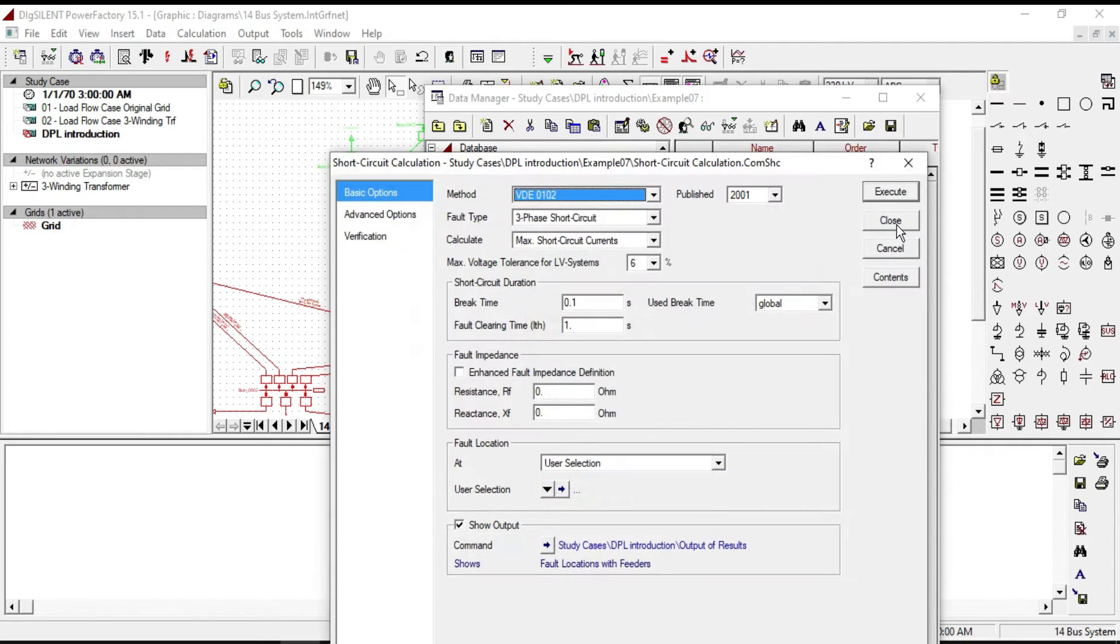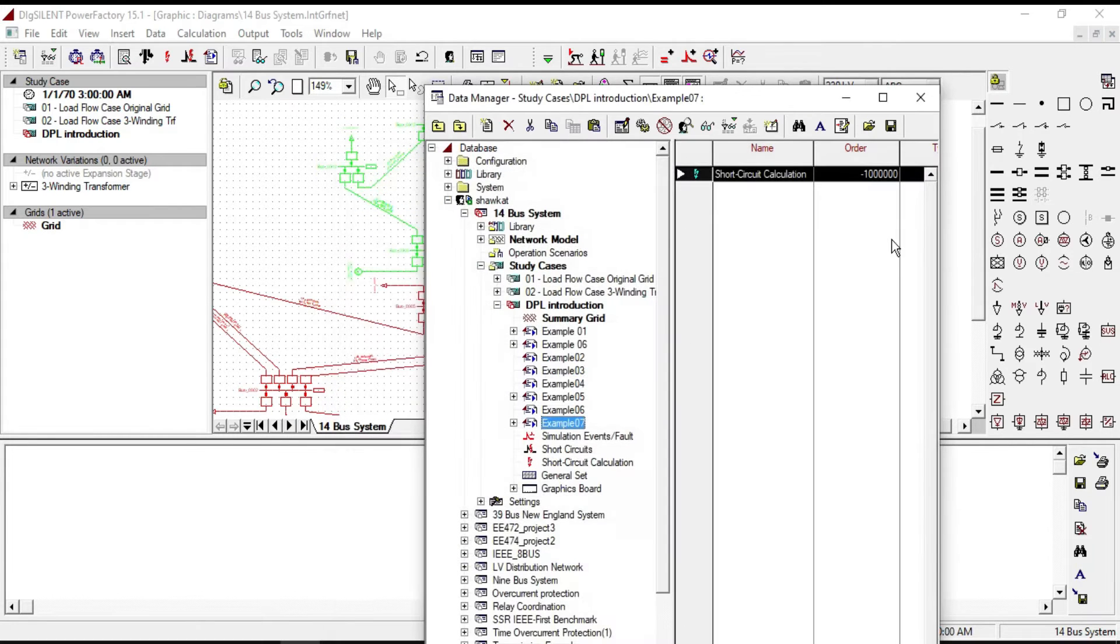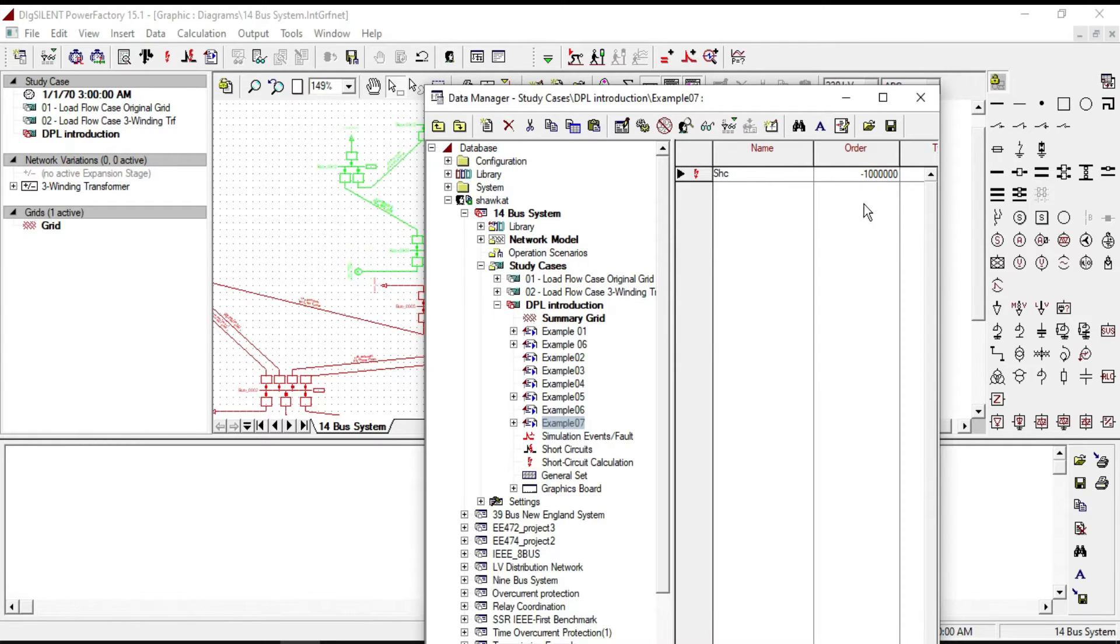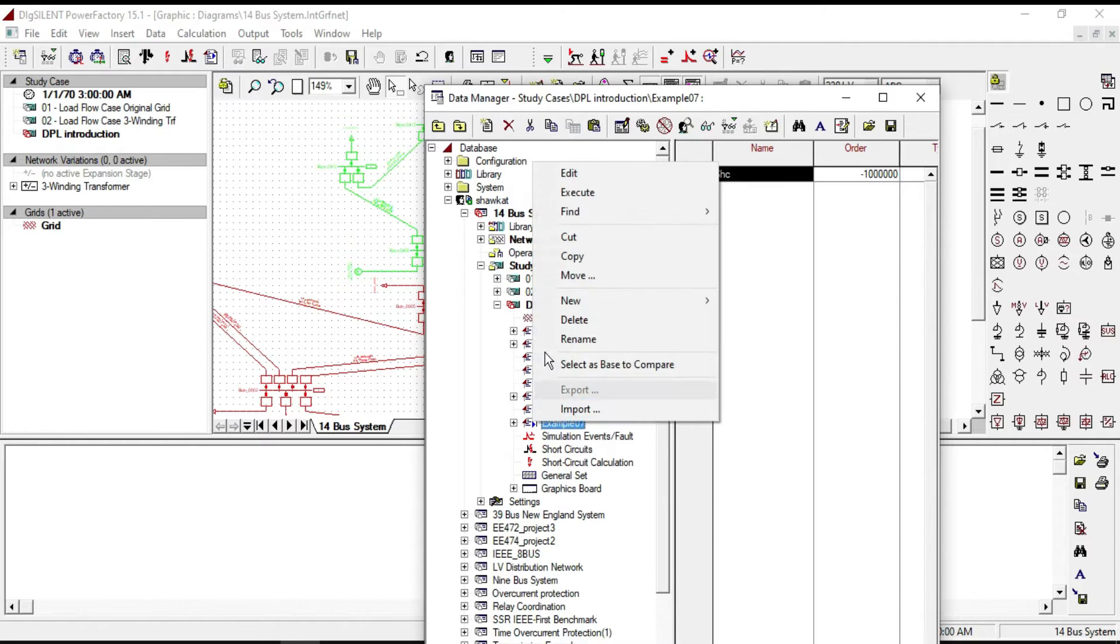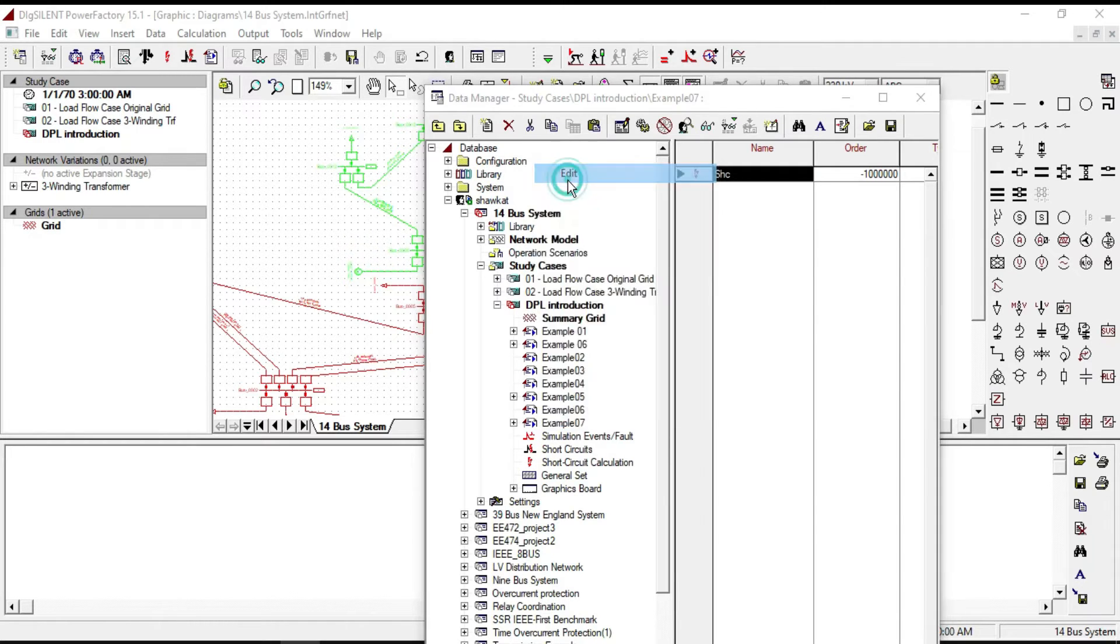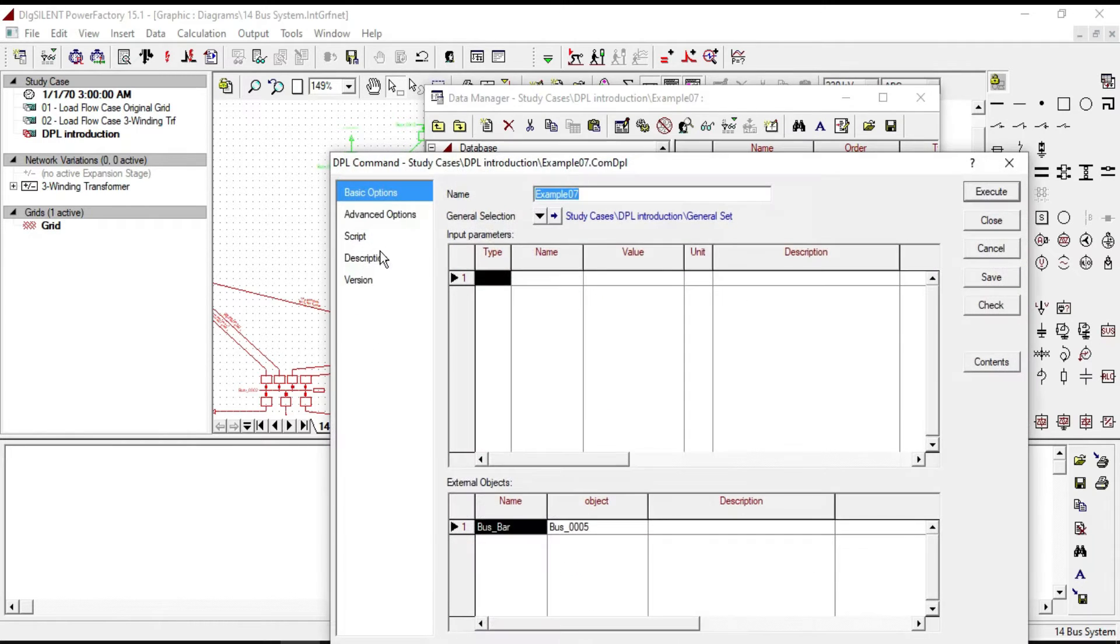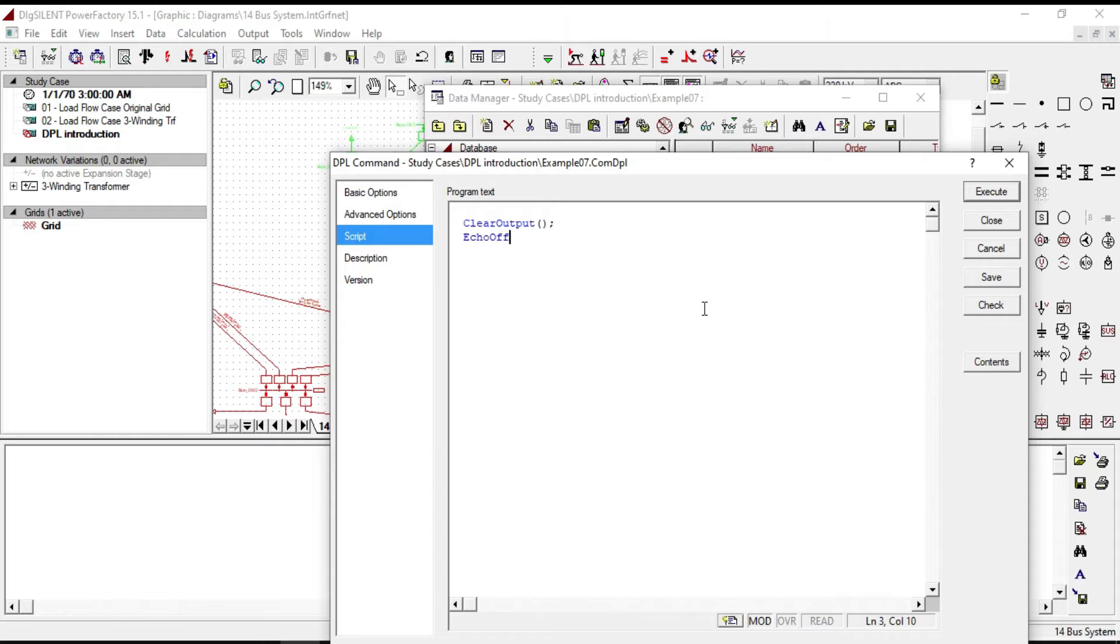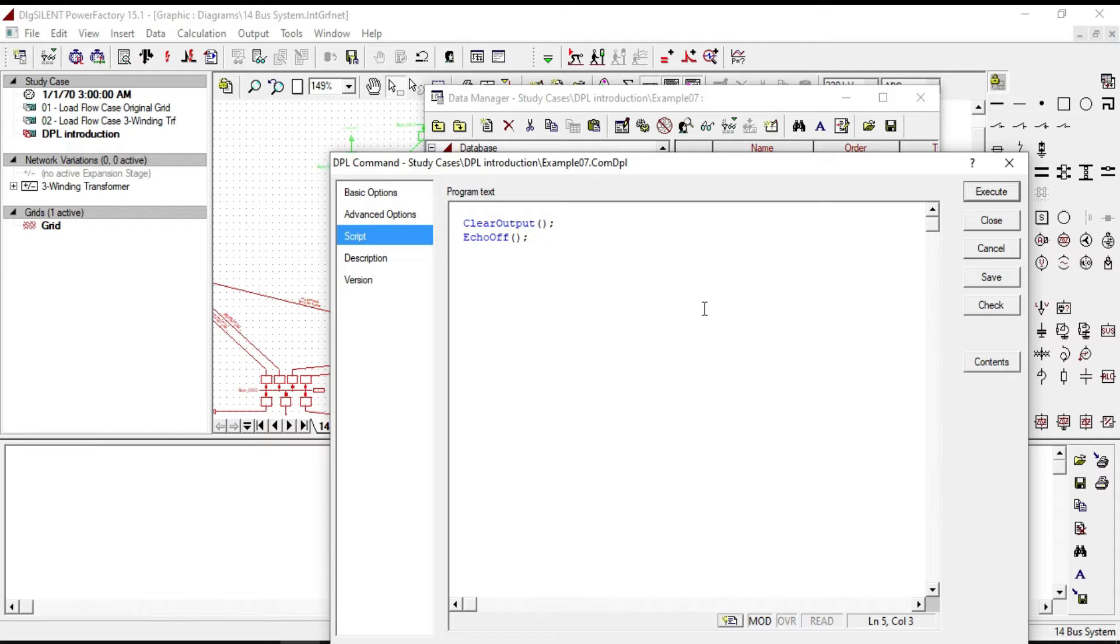Then from the element choose short circuit calculation, click OK, close it, and name it as SHC. Now by using the execute we can access to short circuit command. Go to the script. To clear the output window, let's write code as clear output close bracket semicolon, echo off close bracket semicolon to freeze the user interface.